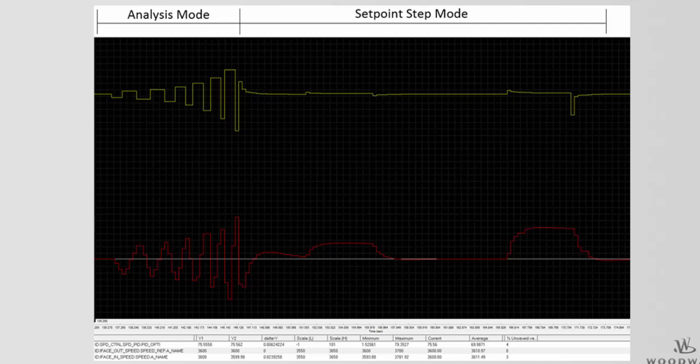The process of finding optimized system dynamics includes two modes: first, the analysis mode, and then the setpoint step mode. This trend provides an overview of the entire optimization routine. The actuator demand is given in yellow, speed setpoint in white, and speed in red. The left portion of the trend is the analysis mode, and the right portion is the setpoint step mode.